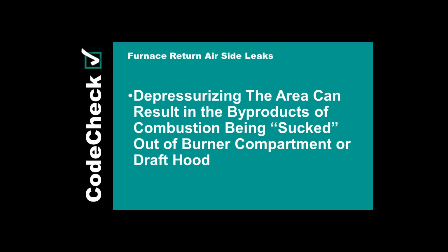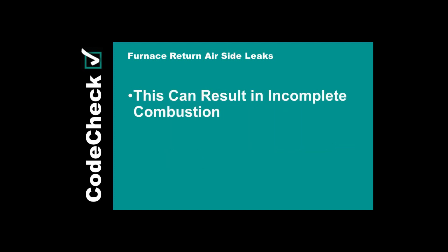You can also move air backwards across the burner assembly. Those burner assemblies were never intended to have air flow in reverse to the direction of the flame. Whenever this happens, you can have incomplete combustion as a result. So either venting back down into the enclosure, or venting and sucking air out of the burner assembly can cause the burner to operate in a manner that produces incomplete combustion.